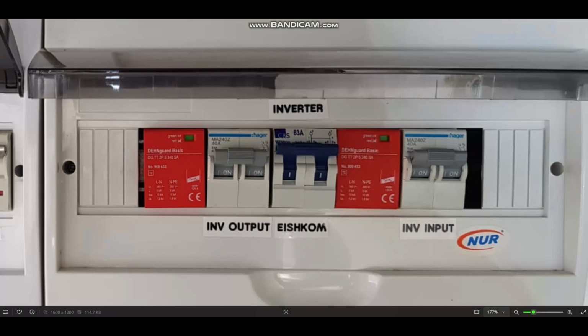You'll notice that you also need a very good changeover switch, and this is in the event that the inverter malfunctions, you need to send a technician over to come and collect or repair. You can bypass from the inverter down to, we did this on request of the customer. Instead of grid power, they asked us to label it Eskom. So this is your second layer of surge protection.